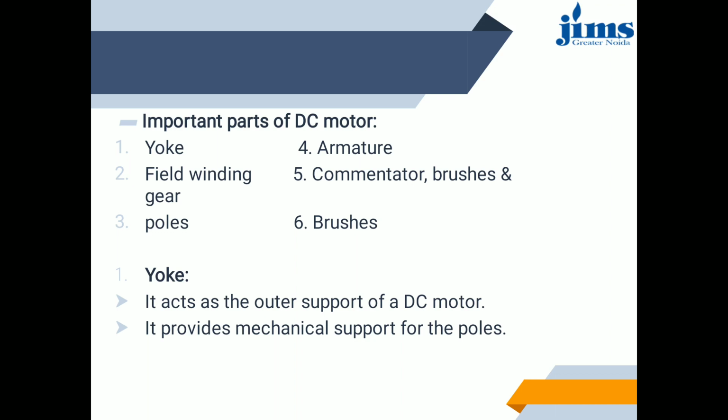A cylindrical yoke is usually used, which acts as a frame of the machine and carries the magnetic flux produced by the poles. In a small machine, cast iron yokes are used because of cheapness, but the yoke of a large machine is invariably made of fabricated steel due to its high permeability. The pole core is usually of circular section and is used to carry the coils of insulated wire carrying the exciting field current. The pole shoes act as a support to the field coils and spread out the flux over the armature periphery more uniformly, and also, being of large cross section, reduce the reluctance of the magnetic path.